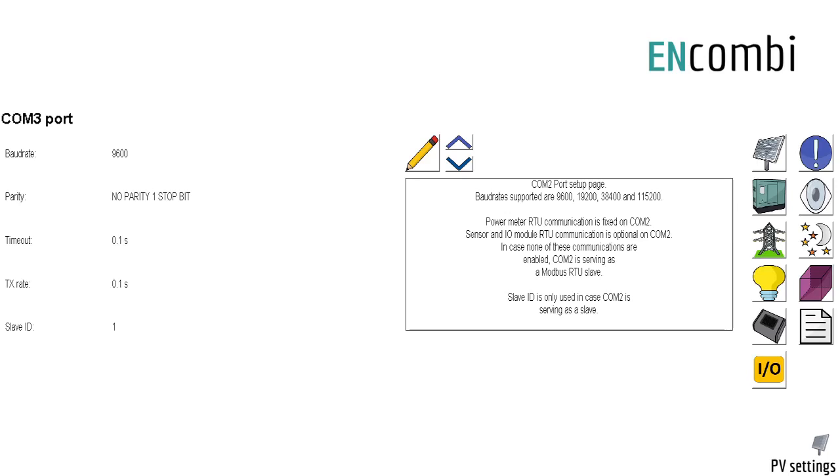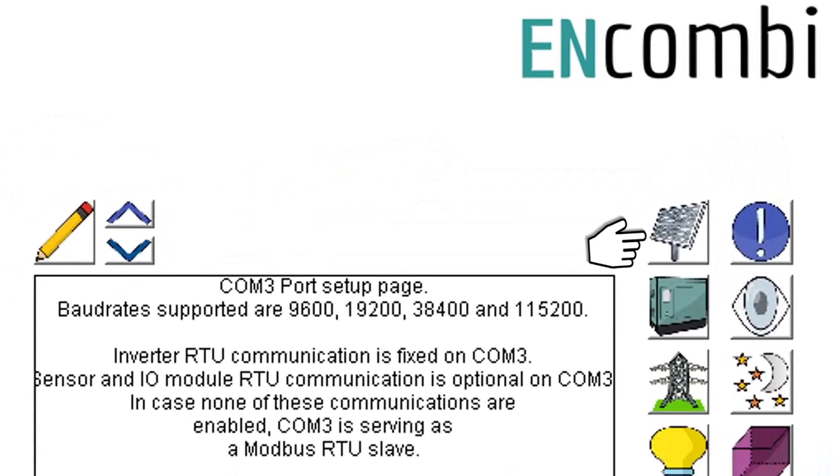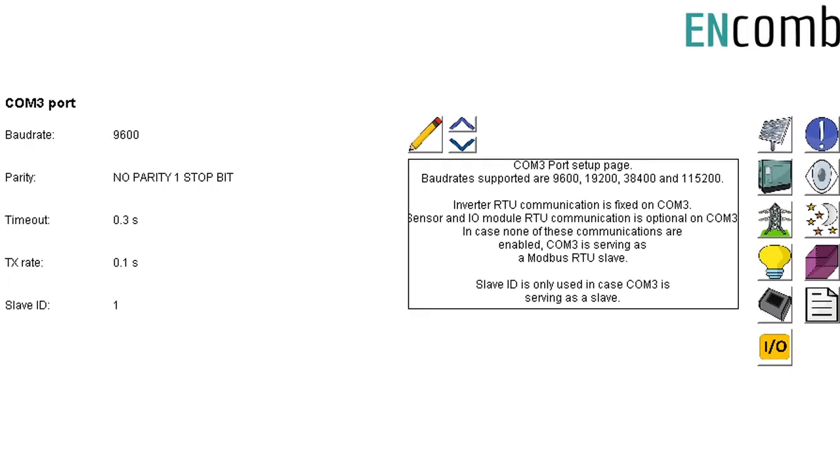PV Modbus RTU communication happens only via COM port 3 of ECPv2. You have to select COM port 3 before moving to the PV settings. Use the PV editing option for all PV related settings. Through your assigned settings on PV, the ENcombi controller receives data and performs the synchronized control of PV production.